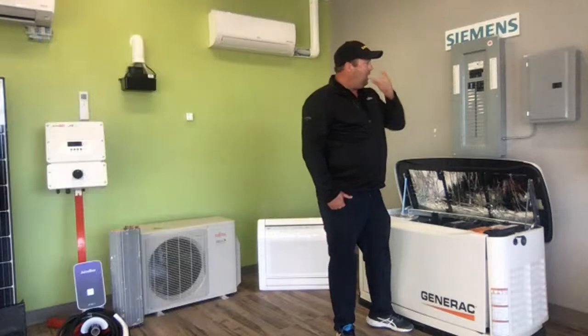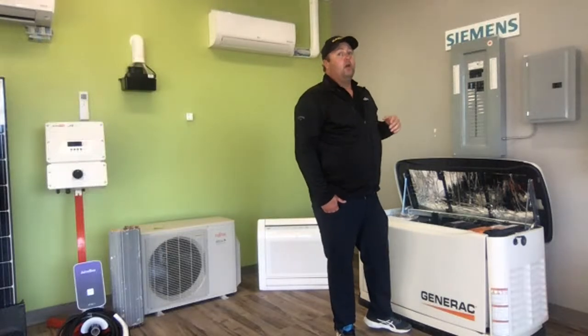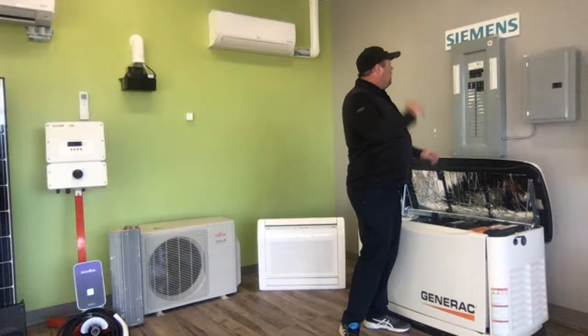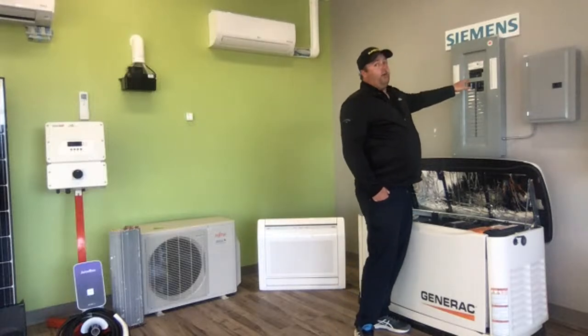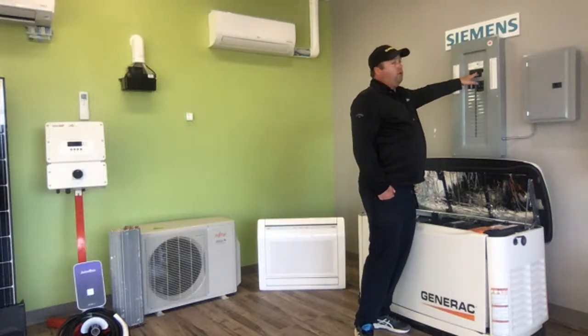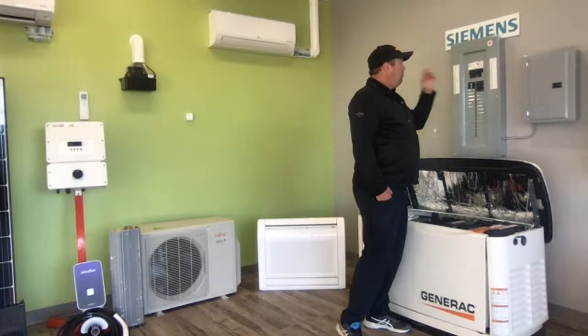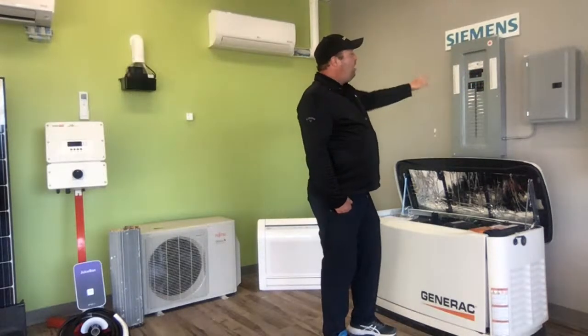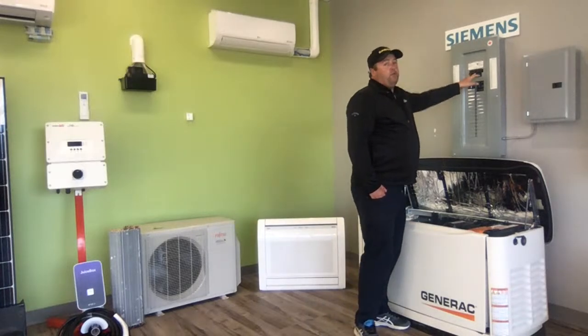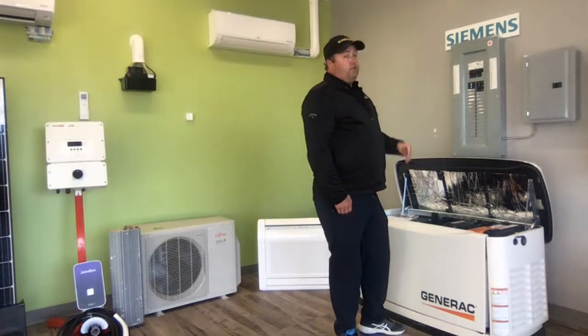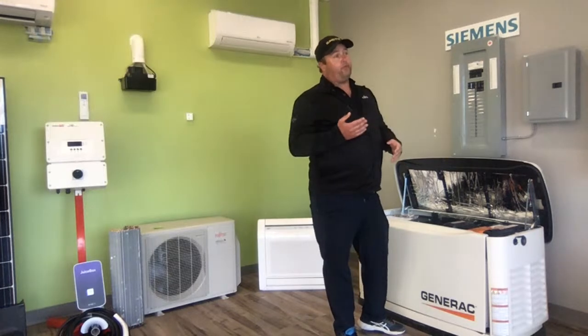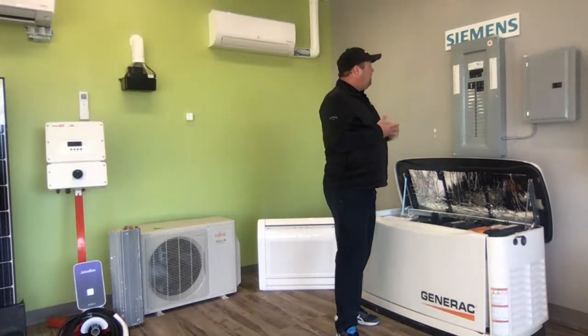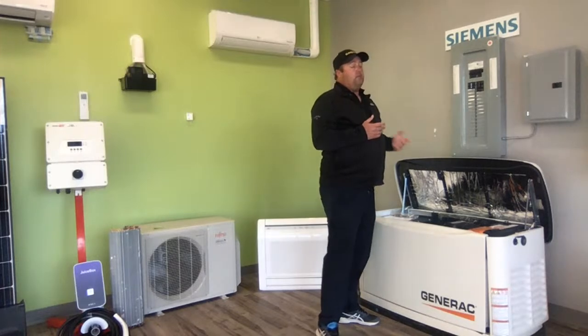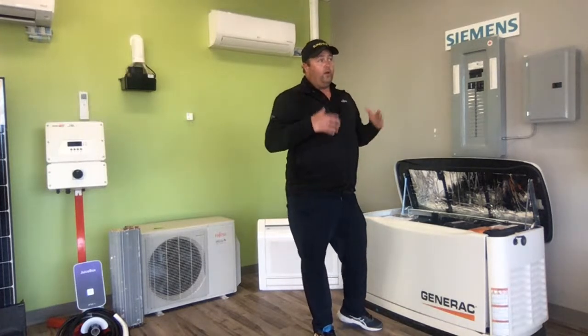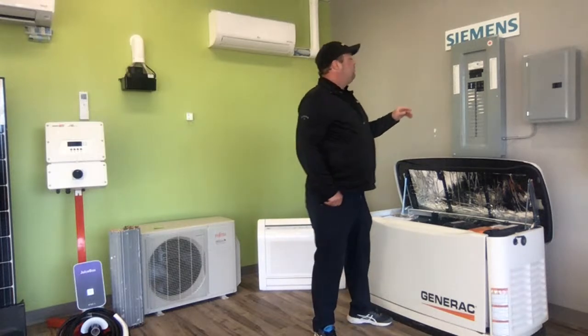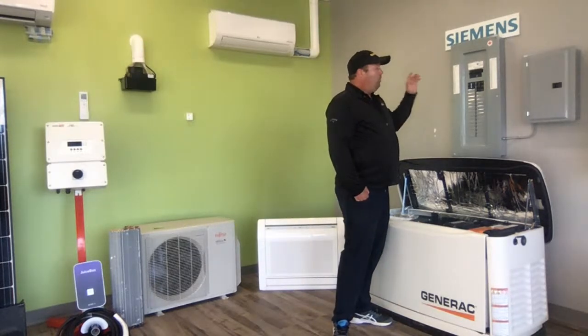This is typically in electrically heated homes because electric heat takes a lot of power. With oil houses, a lot of times you'll have 100, 100, sometimes 125, 125. This doesn't necessarily mean if you have 100 amps you can't do a heat pump—you can still do one, often 2 or even 3. But the caveat is if you're going to keep oil as your backup heat, because you'll always have to have a primary heat source with a heat pump of any kind.